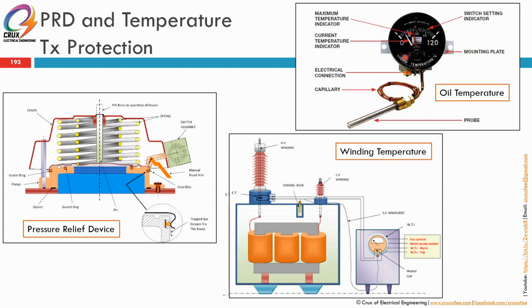When you see it on the transformer nameplate, there will be two ratings. One is the oil temperature rise rating. Another one is the winding temperature rise rating. So normally both of these differ by about 5 degrees, with the winding higher than the oil temperature. Okay, so this oil temperature will not be up to 105, so it will be maybe between 90 for alarm and 100 for the trip setting.